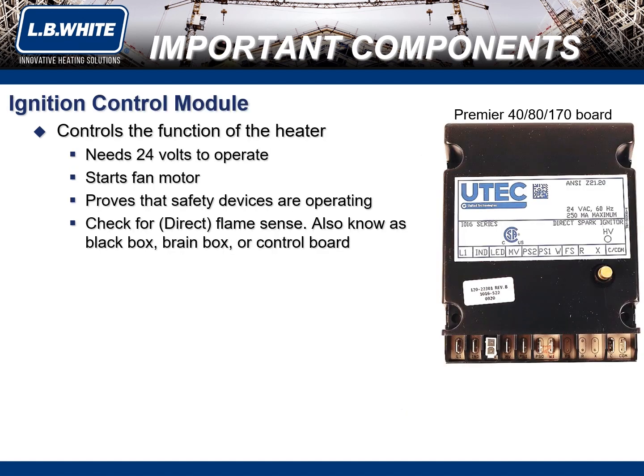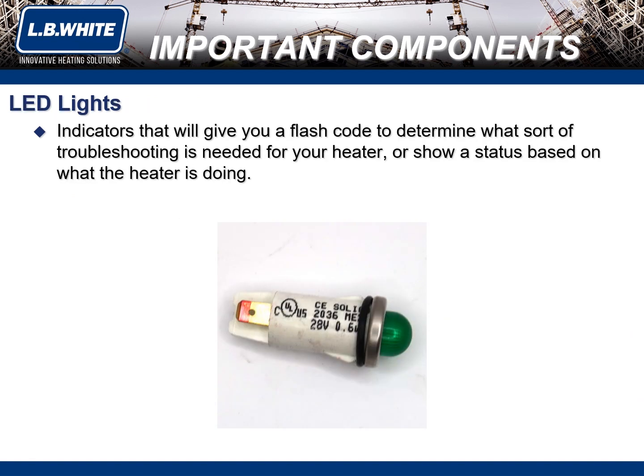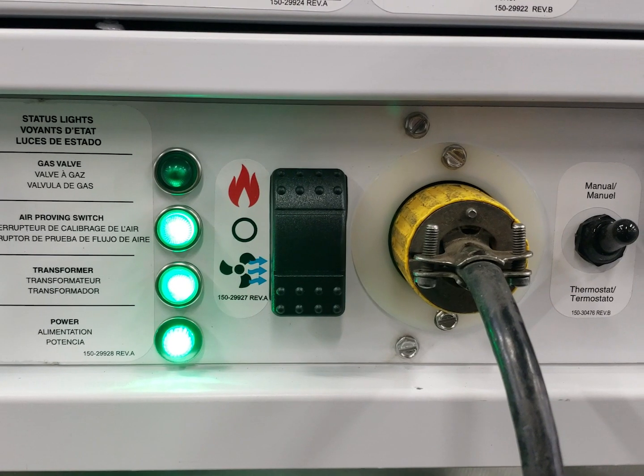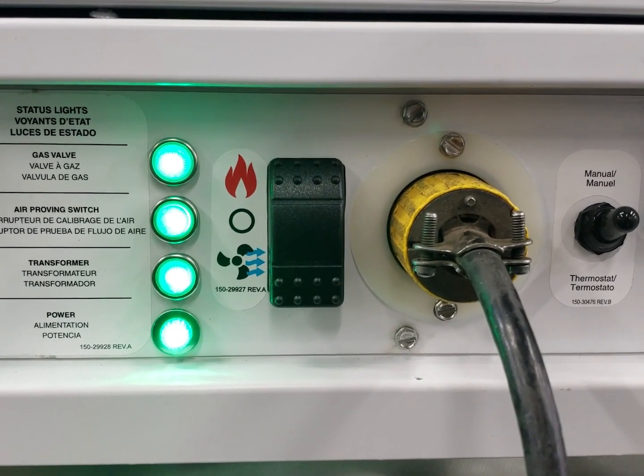An ignition control module, also known as the black box, brain box, or control board, controls the function of the heater. It performs several tasks, such as starting the fan motor, proving that the safety devices are operating, and checking for direct flame sense. LED lights are indicators that will give you a flash code to determine what sort of troubleshooting is needed for your heater.